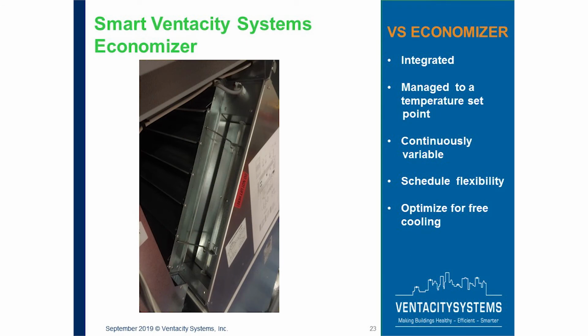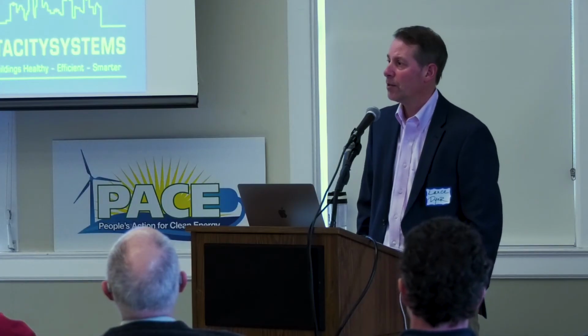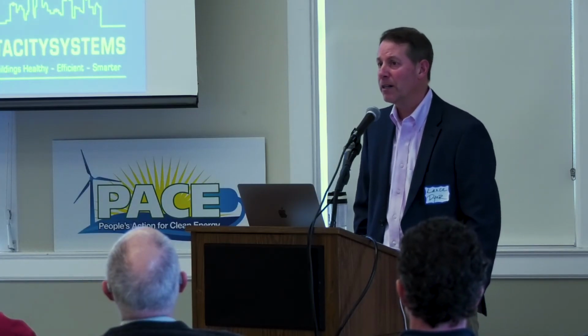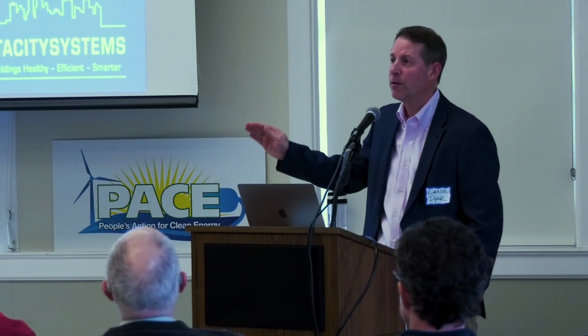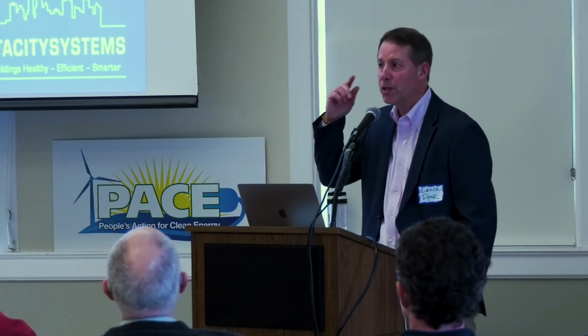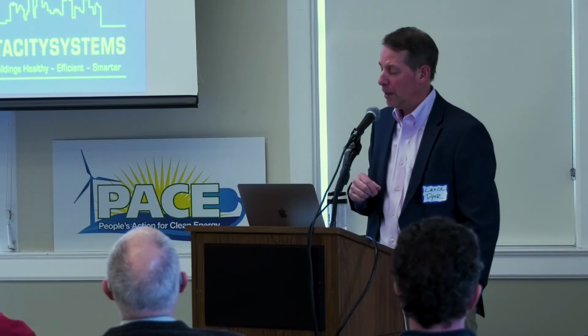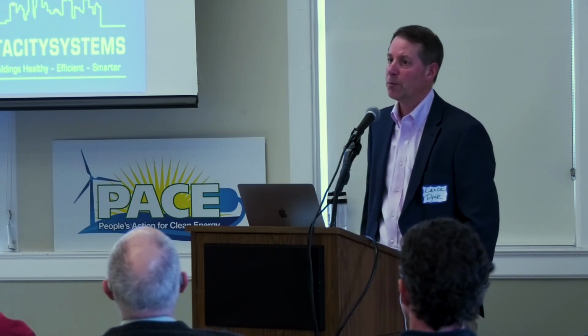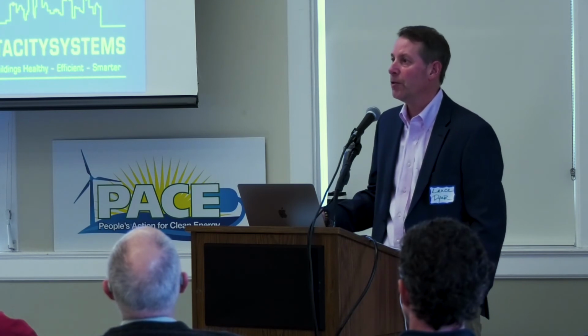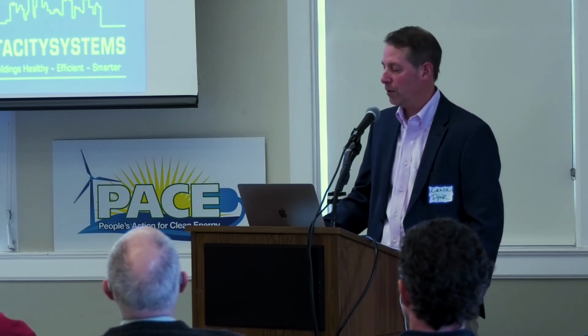Nice thing about high efficiency ventilation is it allows for a smart ventilation system. It allows that you can do demand control with it, meaning that you can set this up on temperature, you can set this up on CO2 levels, so it'll monitor CO2 and vary its amount of airflow into a space based upon who's in that classroom and what they're doing. You can also do it based upon humidity as well. So depending upon the application that you have in the room that you're in, you have all those available.